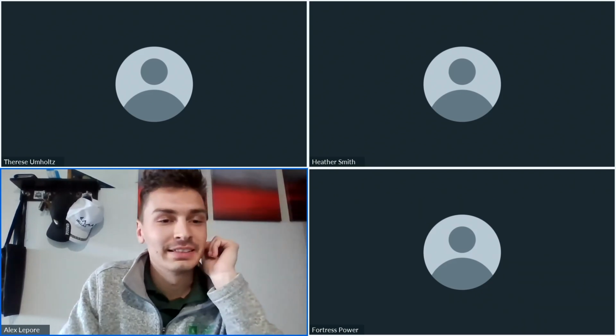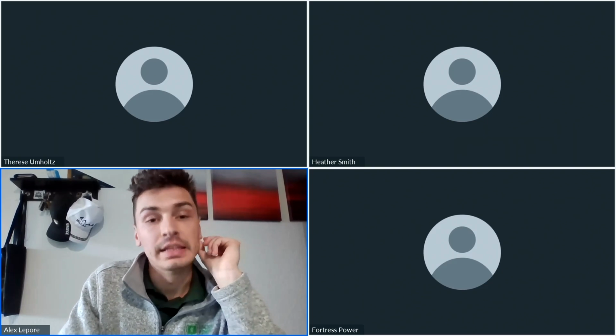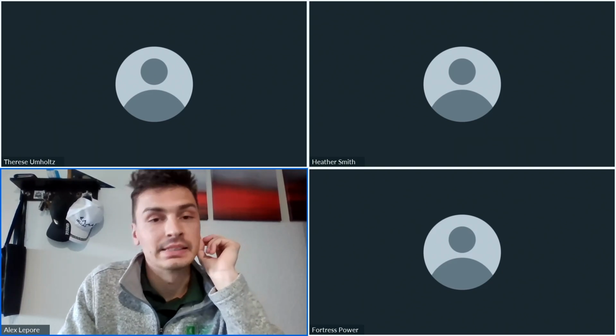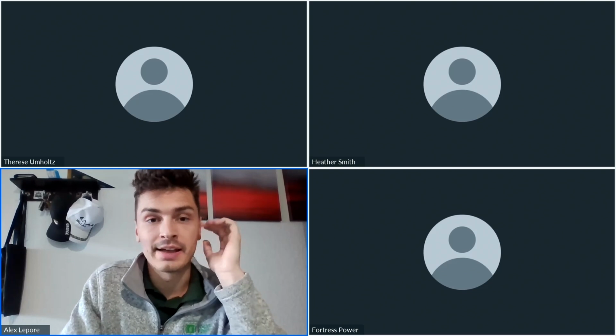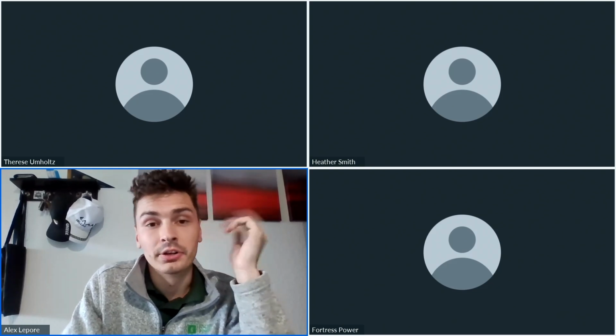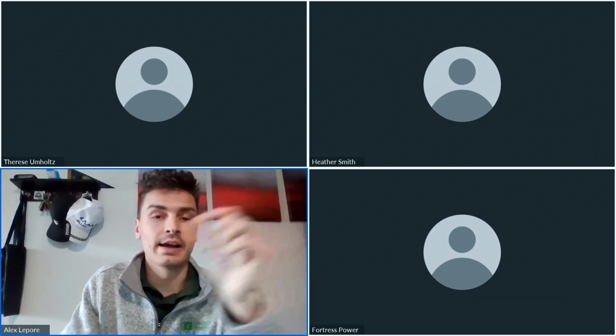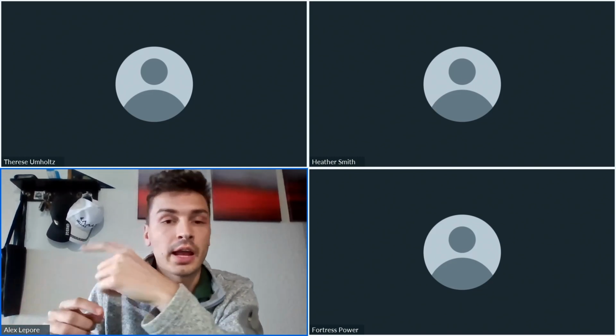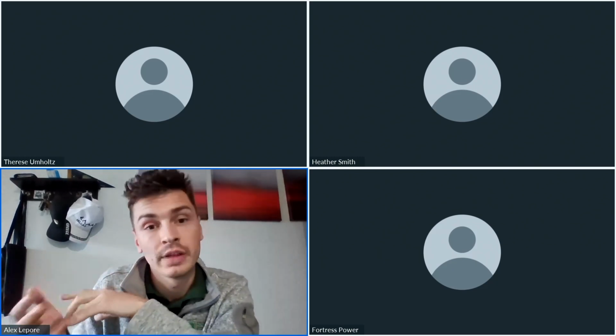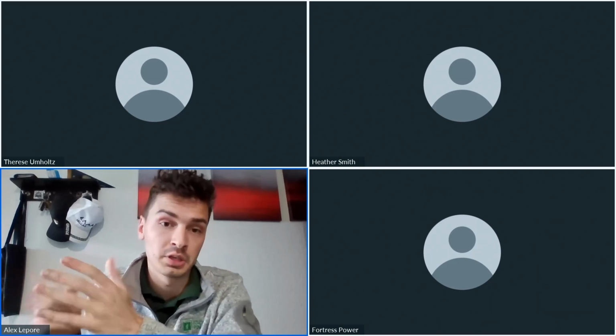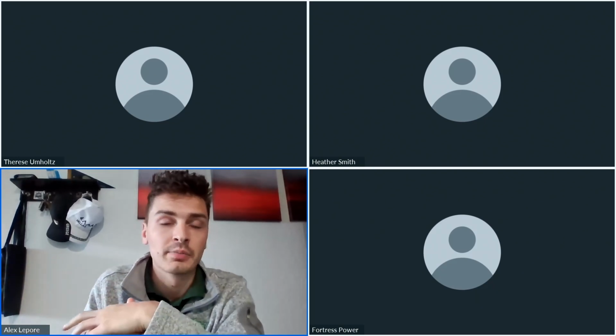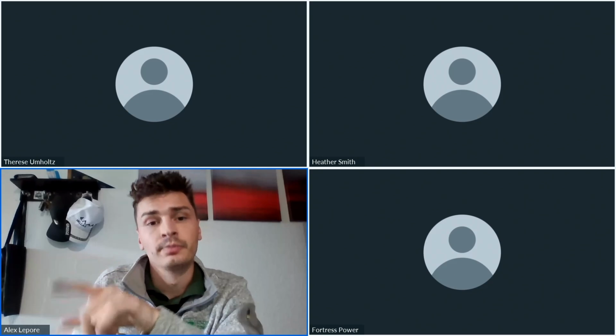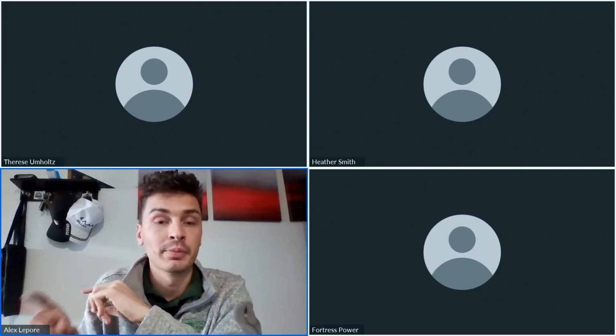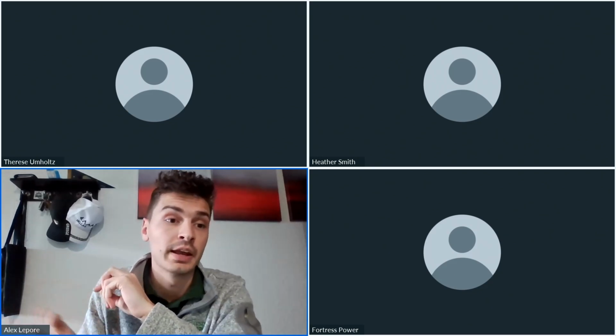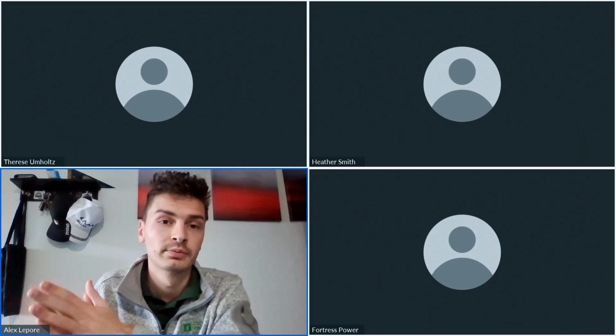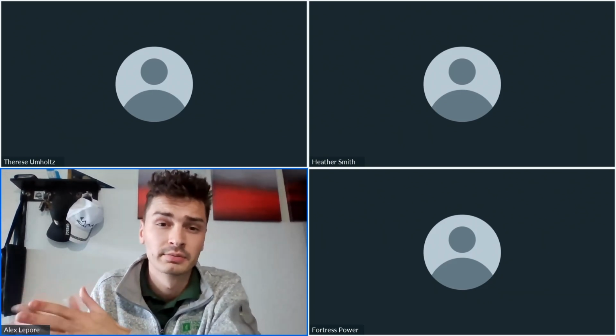Can I program the NV to take advantage of time of use rates with my utility? Yes, you can, though it won't be anything fancy, Kerwin. I know you have an eForce, if I remember correctly. So in the NV you'll have the CLP critical load panel, and you can set up times for the NV to discharge to that load panel during, say, San Diego's peak hours, 5 to 8. I'd recommend checking our manual's settings portfolio so you can adjust those settings to take advantage of offsetting time-of-use rates with your system.